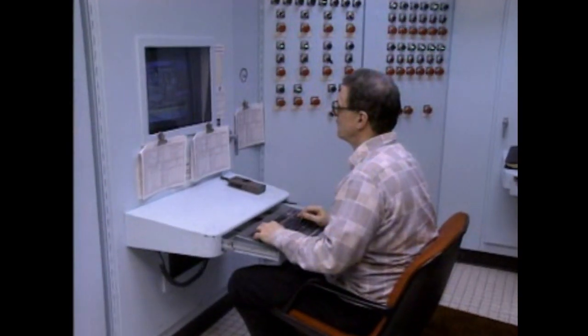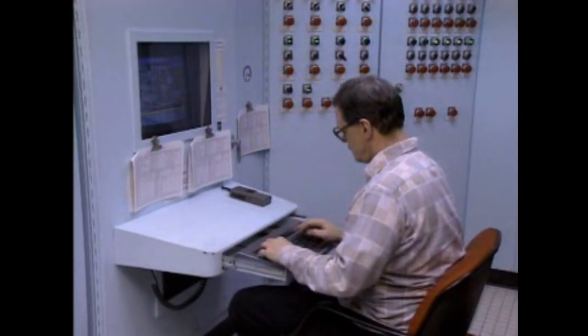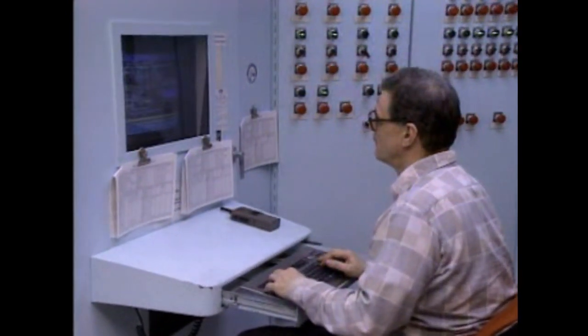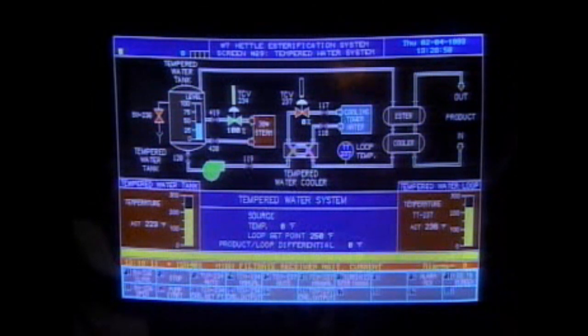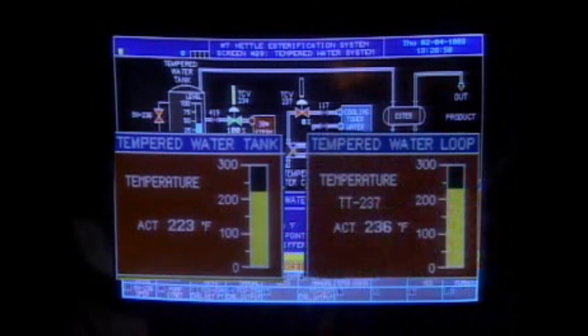When a heat exchanger is in operation, operators must routinely check the unit to ensure that it's operating properly. This may include checking temperature and pressure instruments to make sure that their readings are within normal operating ranges, as well as checking the condition of the heat exchanger itself. By checking a heat exchanger's temperature instruments, an operator can tell how the temperatures of the fluids change as they pass through the unit. These values can also be used to determine the difference in temperature, or delta T, for each fluid. The delta T can be used to see if the unit is operating properly.